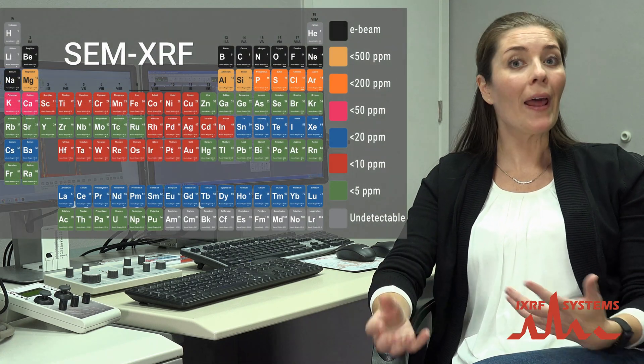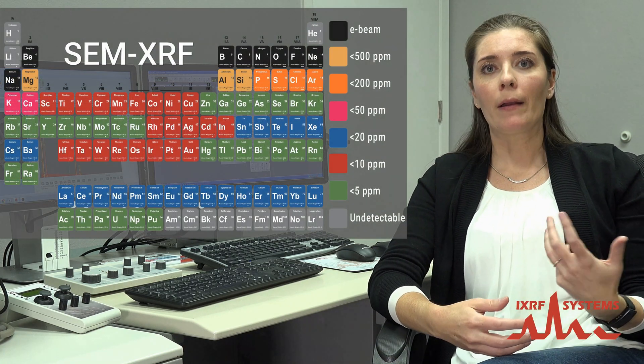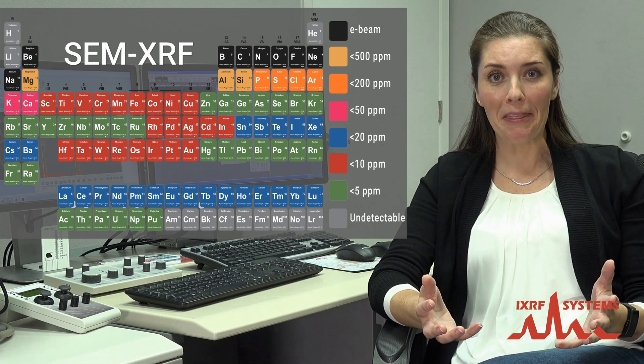Having good quality standards is great for building an empirical calibration, but what if you don't have access to standards — can you still do quantitative analysis? We have incredibly powerful software that can actually do standardless quantitation. The software is going to look at the elements in your spectrum, take into account what energy they were collected at, take into account inter-elemental effects — essentially a lot of fancy math — and that math is going to give you standardless quantitation with really good results according to what's in your material.